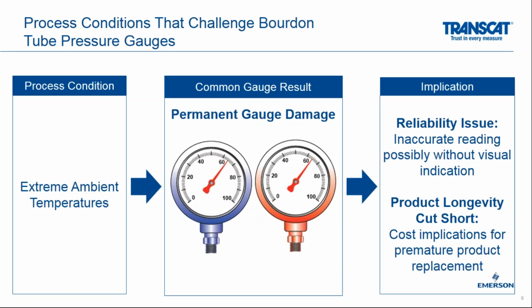Another common thing is extreme temperatures, extreme ambient temperatures. You imagine many gauges are outdoors, and whether you live where I do in Minneapolis or even in Houston, there can be 100 degree temperature changes even within a day, and this can really put strain on gauges. These are made mechanically, and mechanical things expand and contract based on changing temperatures. And you can get some permanent gauge damage if you go beyond temperature limits or simply just strain it too much. From a reliability standpoint, you certainly have inaccurate readings without really a good way of knowing that it's inaccurate. And then from a product longevity standpoint, at some point, those temperature fluctuations can cut the longevity of your gauge short, ultimately meaning you need to replace it.